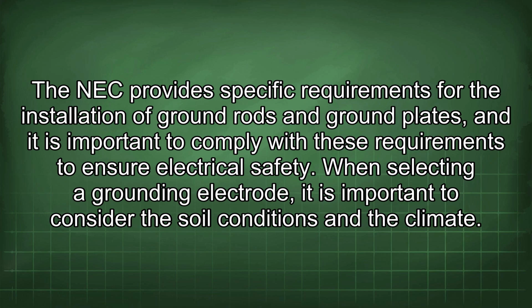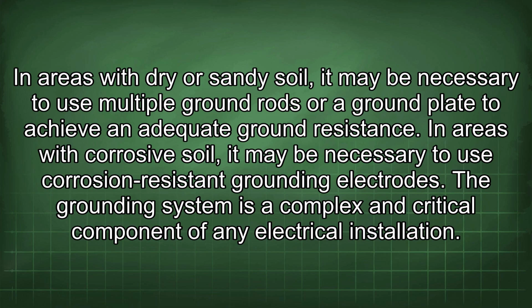When selecting a grounding electrode, it is important to consider the soil conditions and the climate. In areas with dry or sandy soil, it may be necessary to use multiple ground rods or a ground plate to achieve an adequate ground resistance. In areas with corrosive soil, it may be necessary to use corrosion-resistant grounding electrodes.